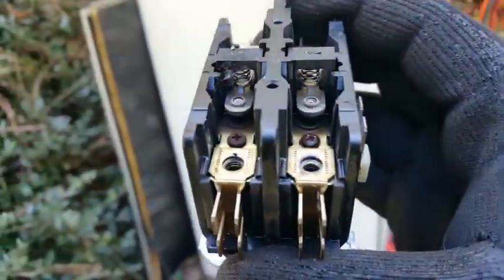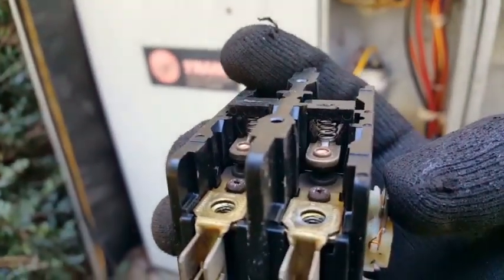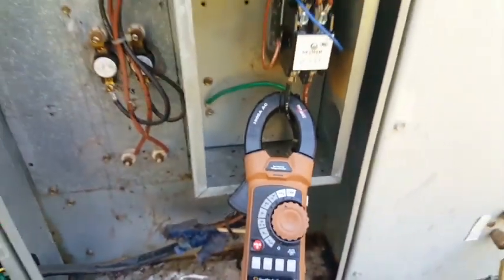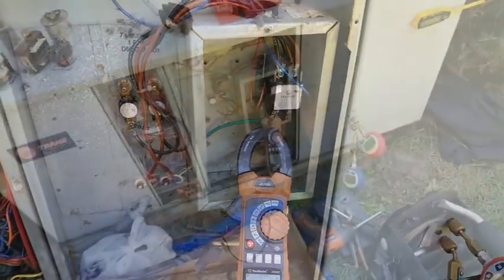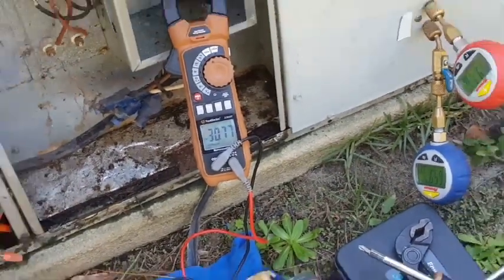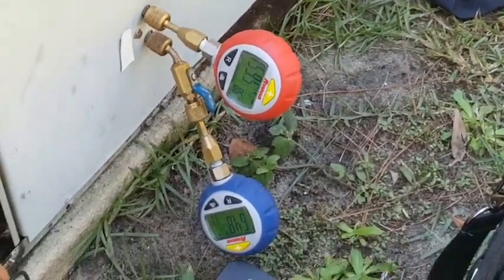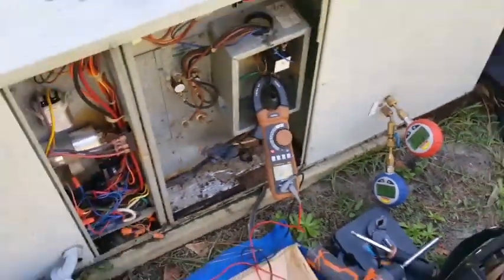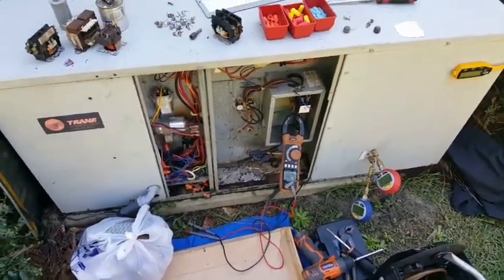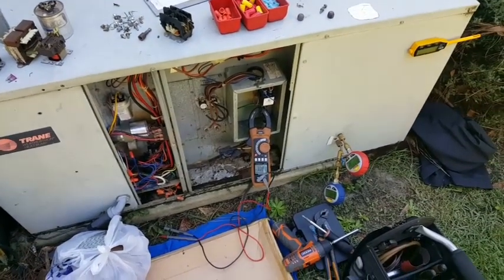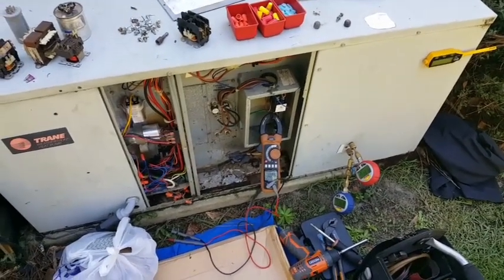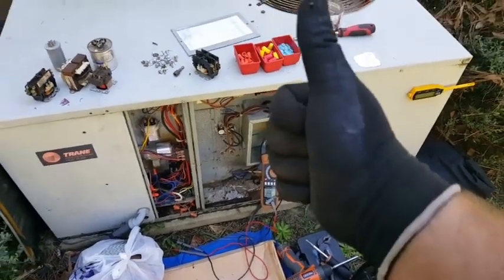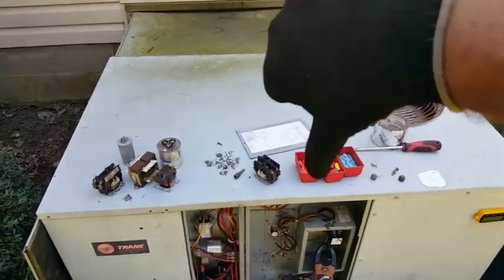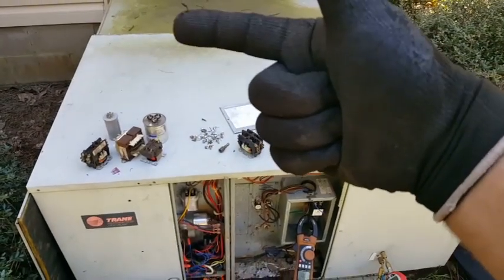Have a new contactor in, our old one. They're looking pretty rough down there. Don't want to take any chances. We have it on amps. We're going to test out the heat strips as soon as we start things back up in heat mode. Our heat strip's running now. 8 kW, 7.5 kW, whatever it is. They're running in heat down there. Not too much different than we were before. Just got started though. I definitely smell them running inside the house. I don't see any smoke shooting out the vents. That's a good sign. So the machine gets a thumb of approval. The duct system gets the thumb of dismay. Boop, boop, bloop.